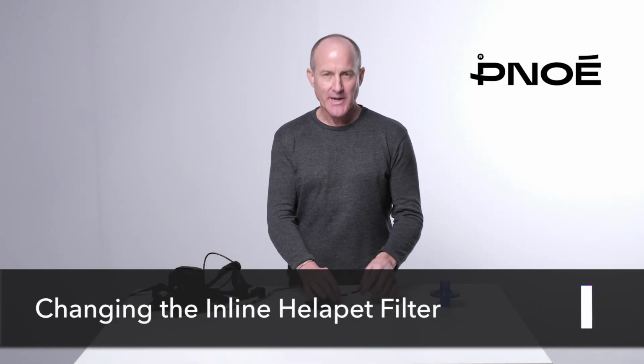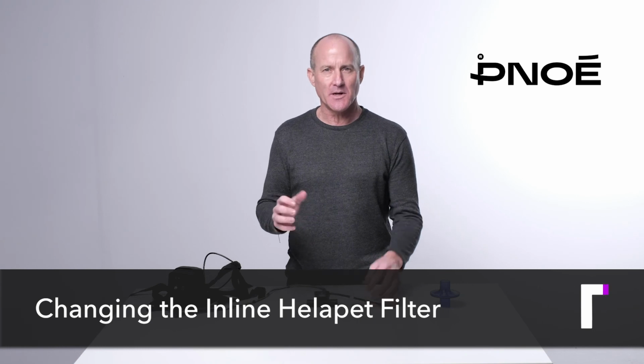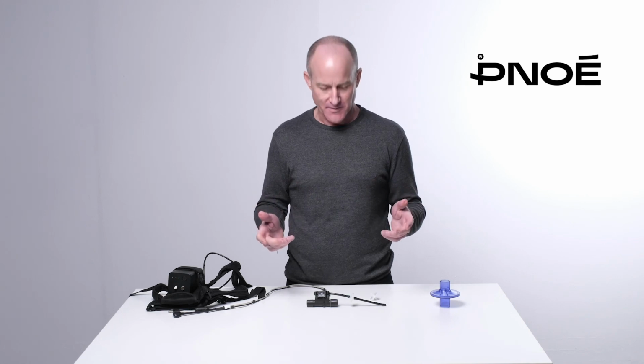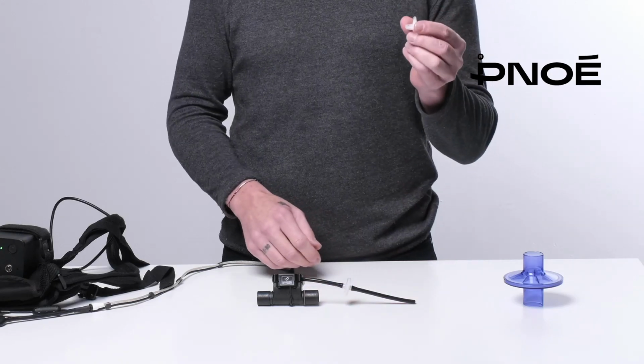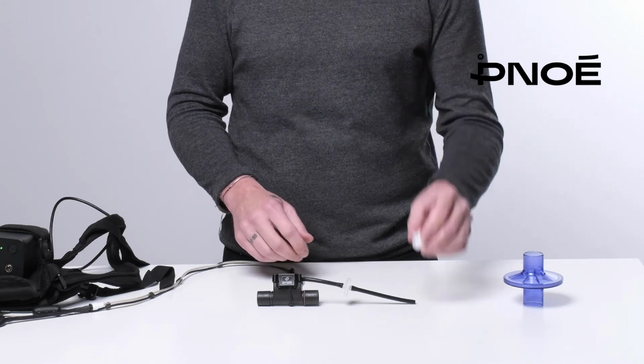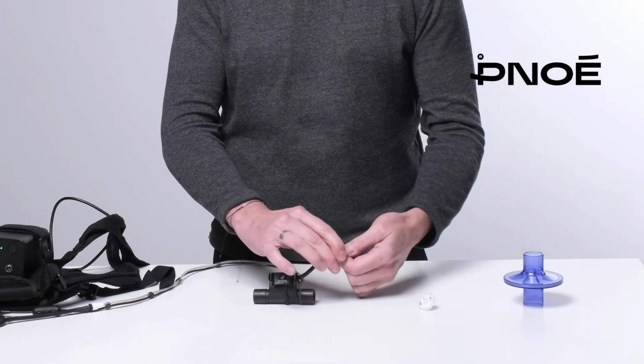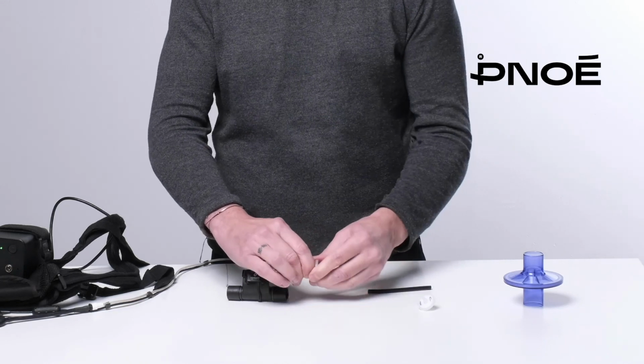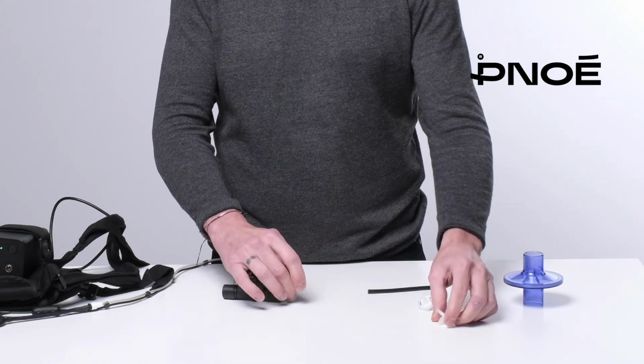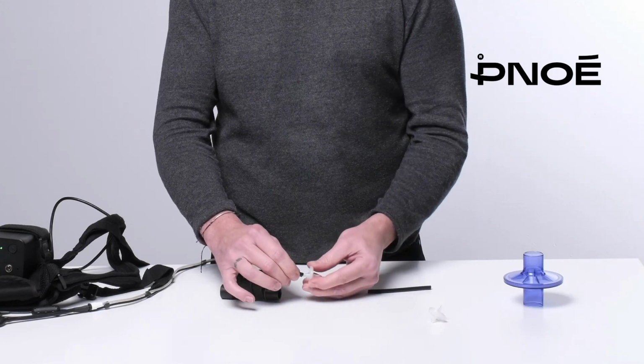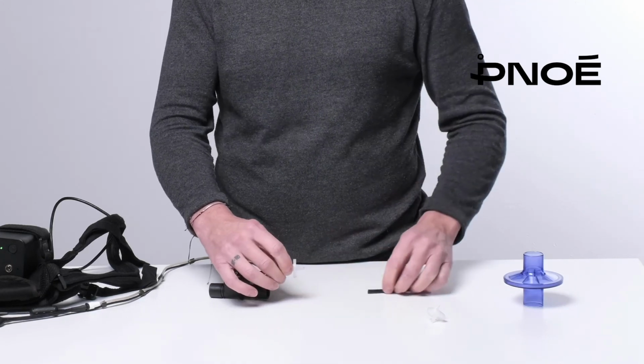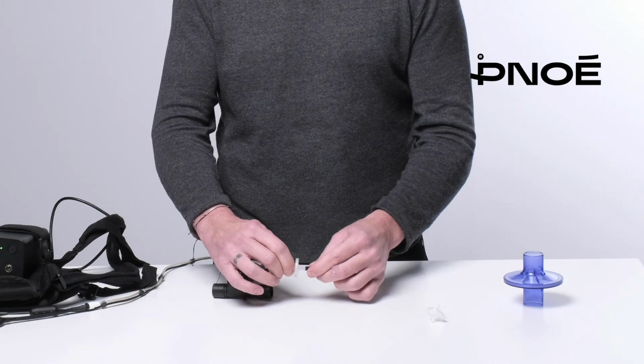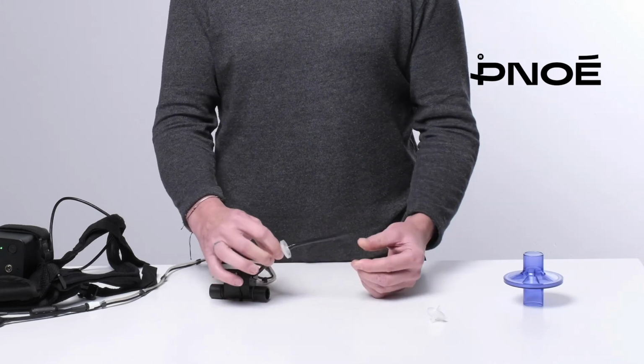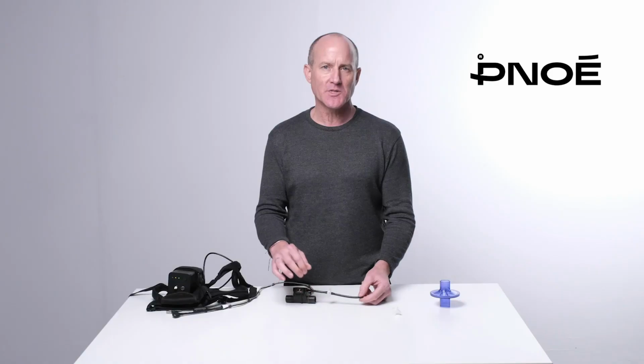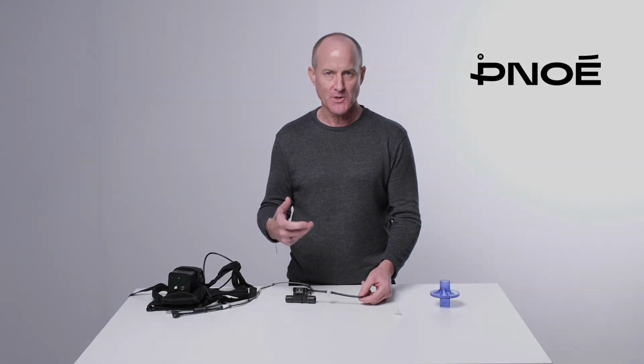Occasionally, you're going to have to change your Helapet filter. What you'll notice is an equal decline in VO2 and VCO2 data, in particular during the fitness test. To change it, you'll have spare Helapet filters available in your kit. You simply remove the black tube, and you can drop in the new filter, making sure that it's well seated. And you're good to go. You should notice a difference immediately in your VO2 and VCO2 numbers.